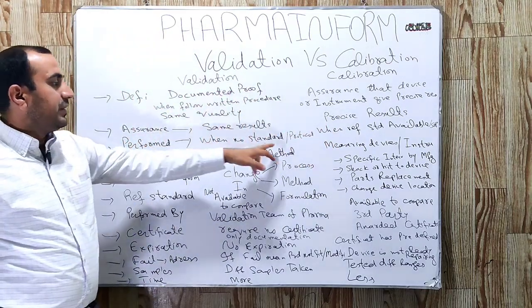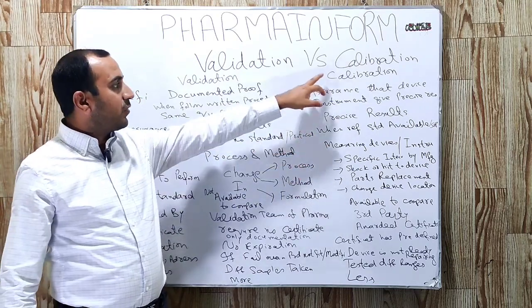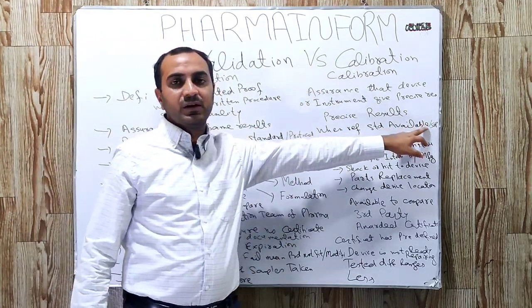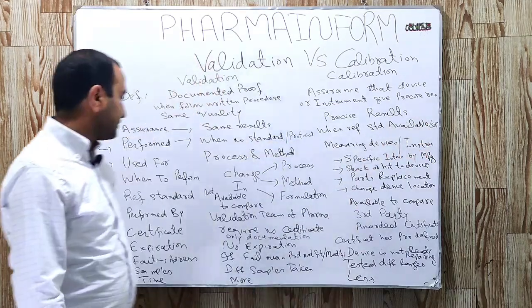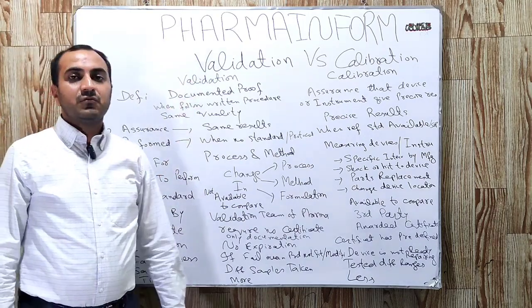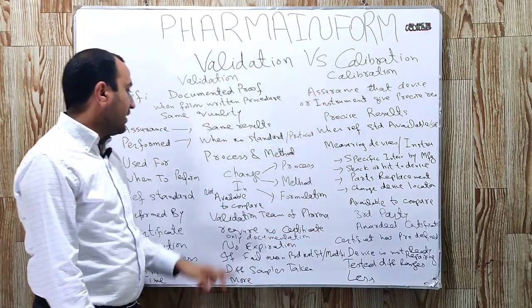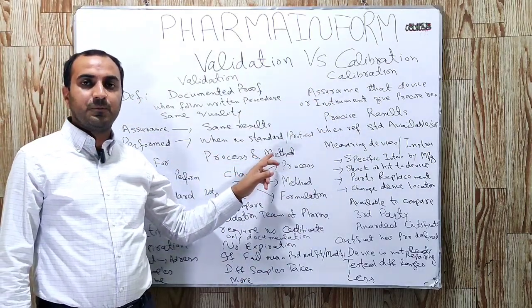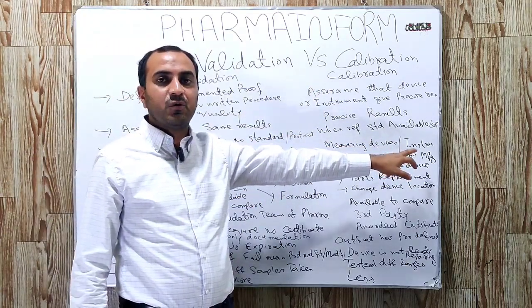Validation is performed by using a validation protocol. Calibration is performed by following a specific standard operating procedure, or SOP. Validation is used for processes and methods; calibration is used for measuring devices or instruments.